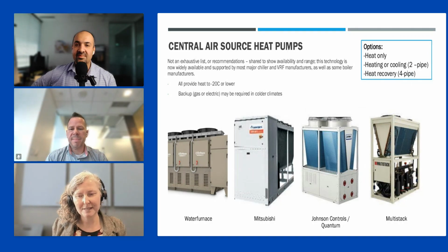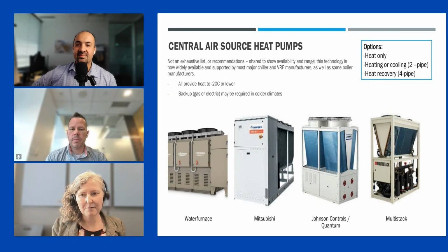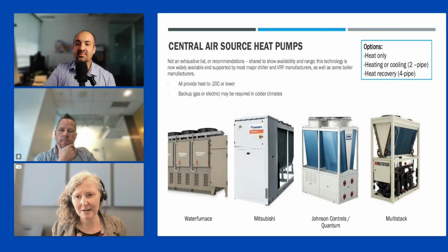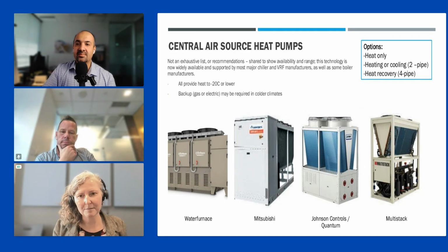So if you haven't been digging into the specs on these in the last 6 months, it's worth going back and talking to everybody, because again, that refrigerant transition has actually taken some names off the market and added others. So people who had been already developing new products, that Water Furnace one up here is a really good example that came on the market in 2025, whereas other people have stepped back. So there are some really good options, and everything that you see on the screen is available to minus 20 Celsius or lower.